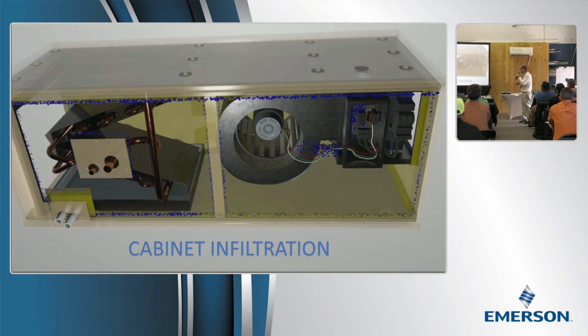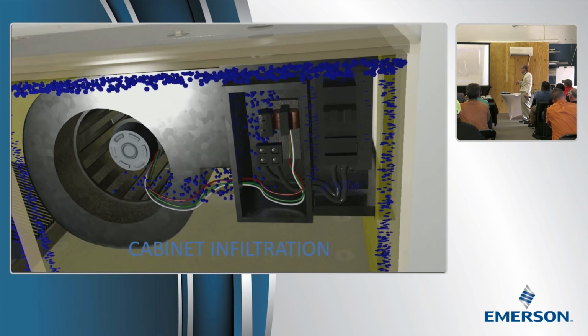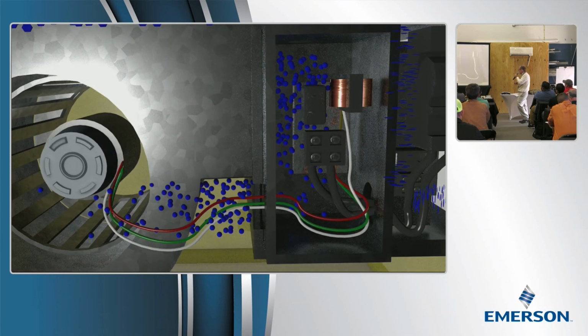Cabinet infiltration. The first thing we're going to look at is the cabinet infiltration that occurs in this electrical box. There's a knockout. That's where the moisture is entering. The transformer has rust all over it. The variable speed board has watermarks and rust on it. How did that moisture get in there? That's at the indoor dew point. Not where the conduit plugs in to the unit. It's dragging the moisture. A Romex connector is not a very good air barrier.